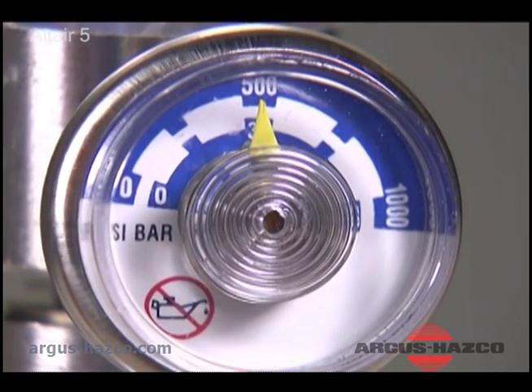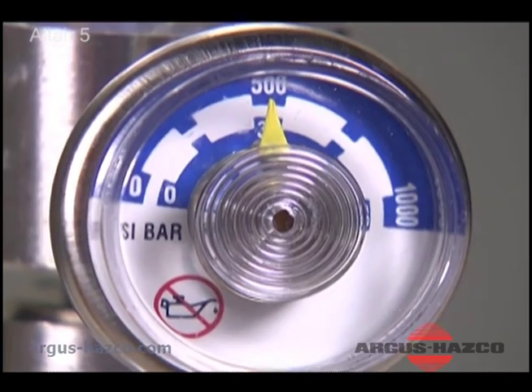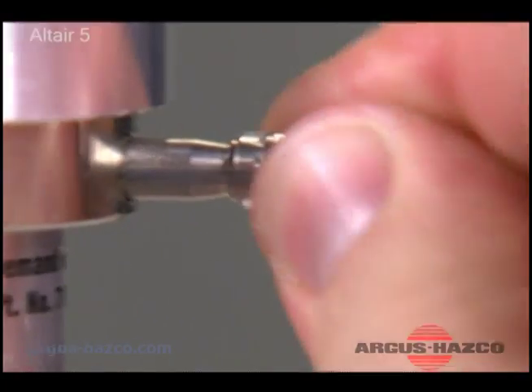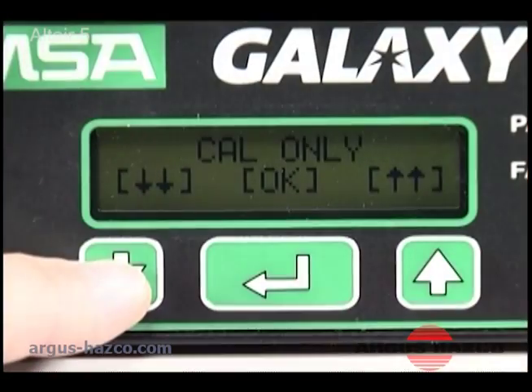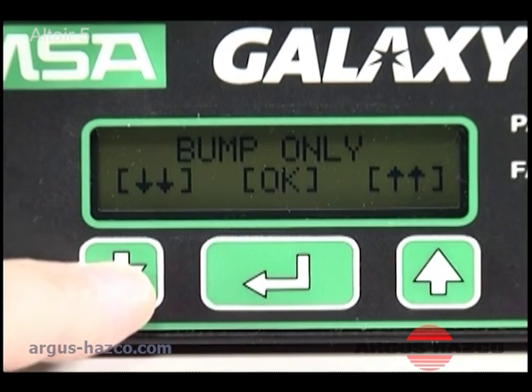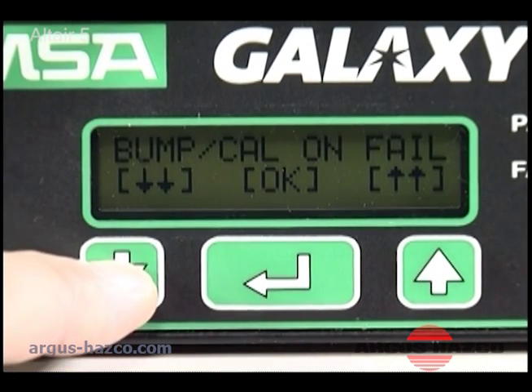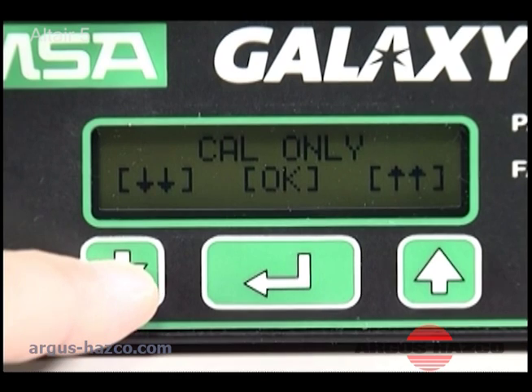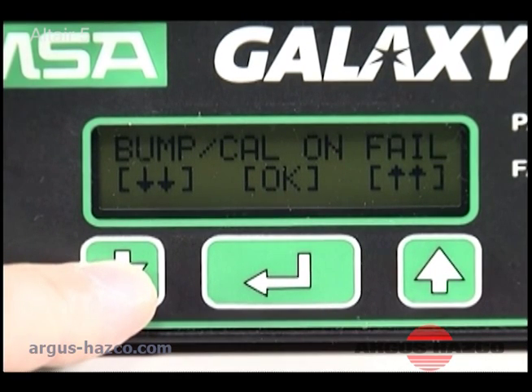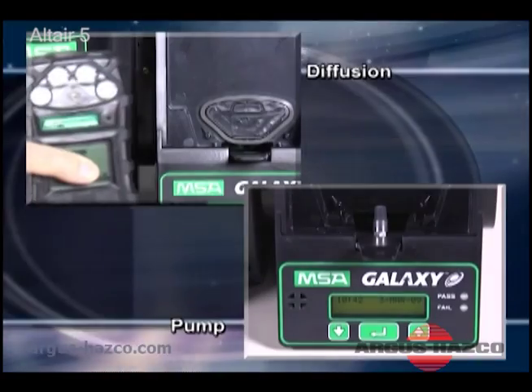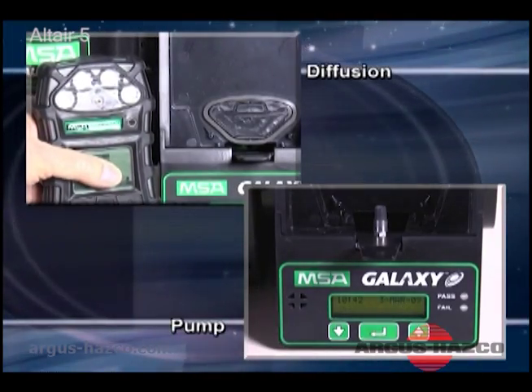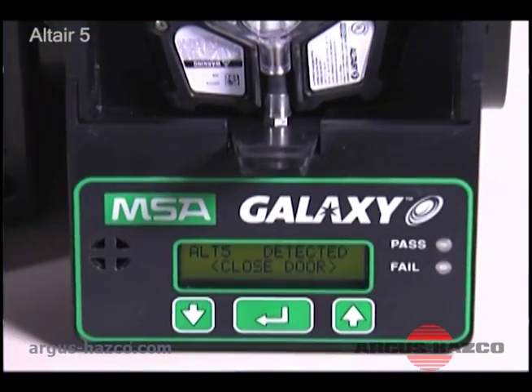Check that the gas cylinders have enough gas and that the demand regulators are connected. Use the scroll up, scroll down, and enter button to select Calibrate Only, Bump Only, or Bump Cal on Fail. If Bump Cal on Fail is selected and the instrument fails a bump test, the test stand automatically performs a full calibration. Place the instrument into the test stand.